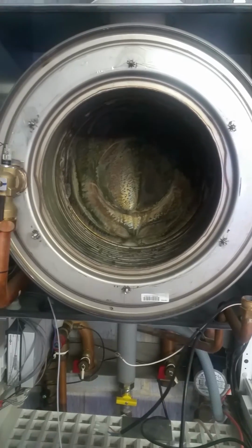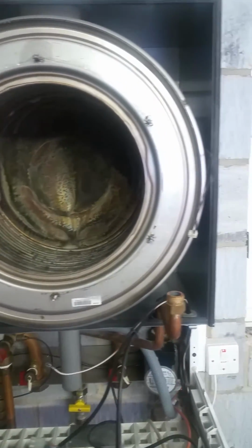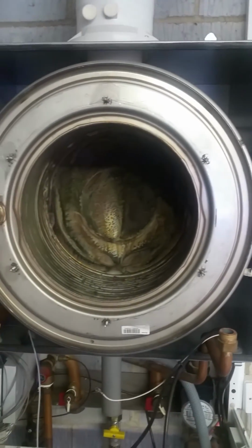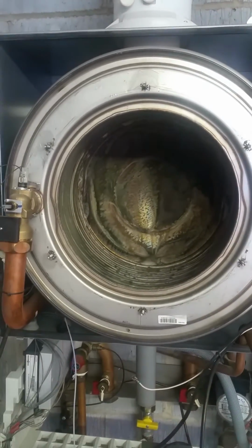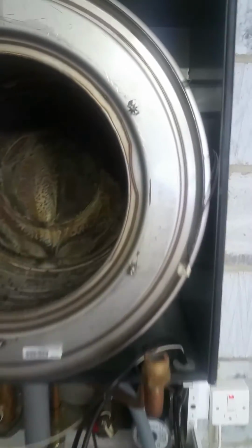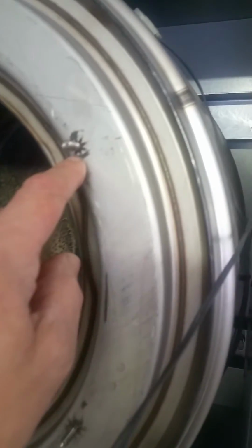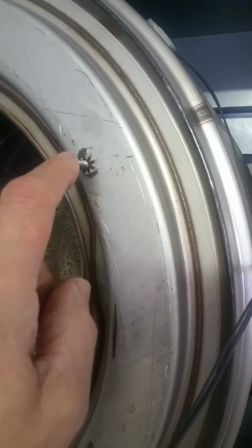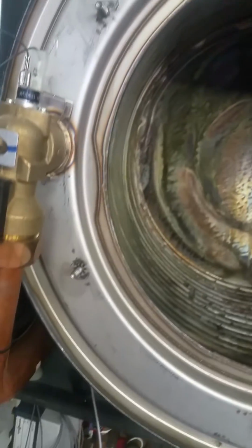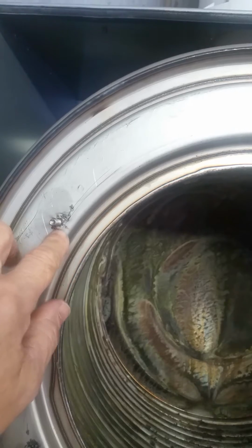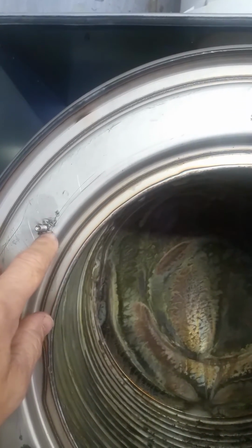So Viessmann have had a few variations of their heat exchanger, and it hasn't been completely trouble-free, but it's been pretty much trouble-free. And the latest version of them, I think, has pretty much got any little problems ironed out. But on some of the earlier models, they had this system where the studs had been welded on the front face of the heat exchanger. And if the bolts were a little bit over-tightened, these would actually just pop off and cause a small crack in the front of the heat exchanger. You get a little tiny leak on the front face here, which would cause a failure of the hex. So I've seen that happen a few times with this method.